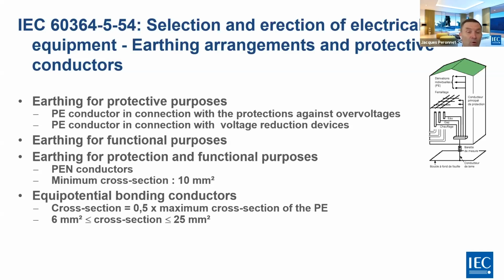We are going to describe, for example, the PEN conductor in case of a TN system. We are also defining the minimum cross section, for example, 10 square millimeters of copper or equivalent. And this is also where we are going to describe the equipotential bonding conductor with a minimum cross section. So it could be half of the maximum cross section of the PE, and the cross section should be at least 6 square millimeters, up to 25 square millimeters for the cable, which is up to this value.